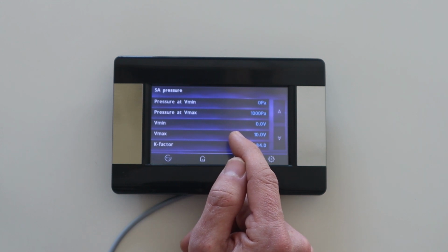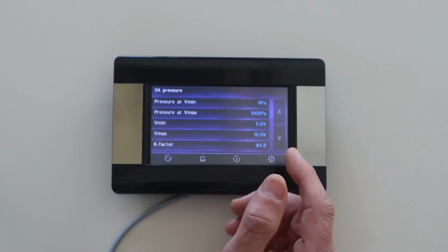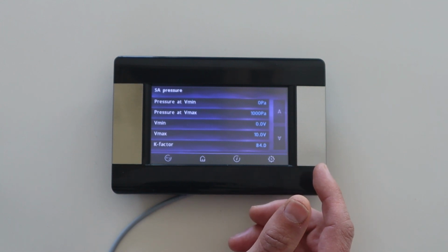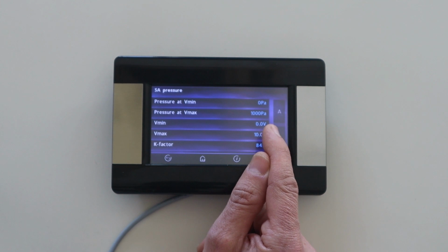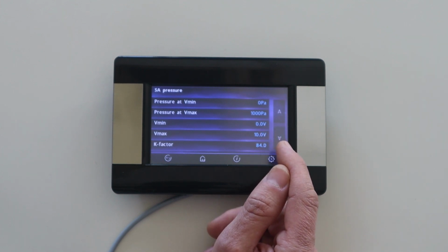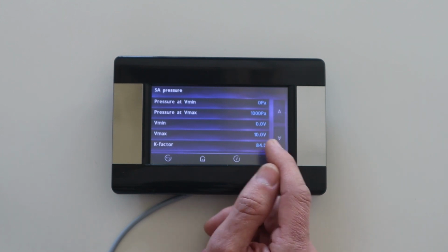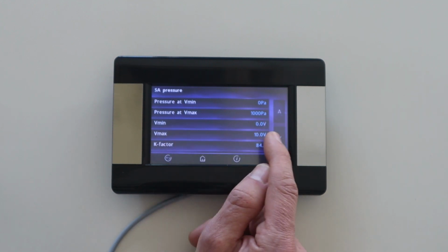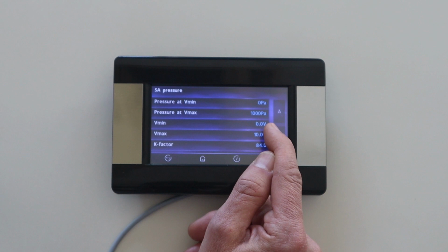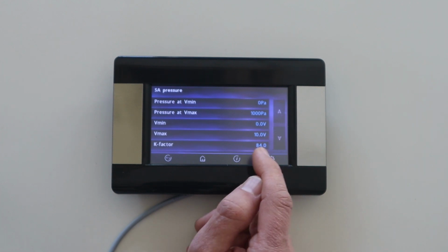Let's say if we have to maintain a pressure of around 250 pascals, the best range to set here and in the TTP is 0 to 500 pascals. This is the general criterion. Okay, and it is also possible to modify the type of outputs coming from the sensor.